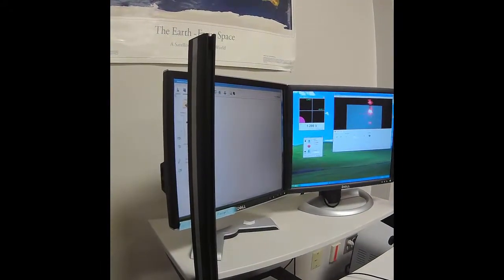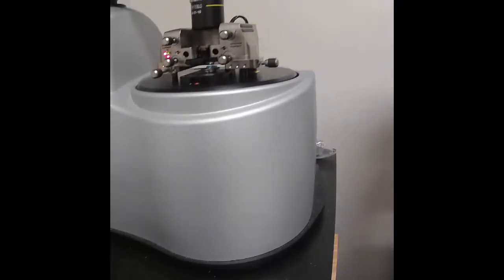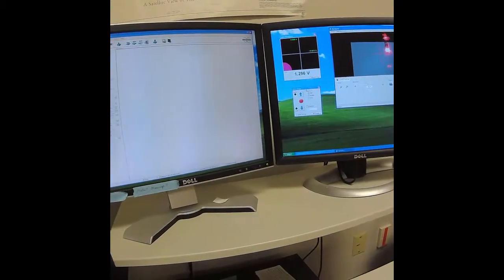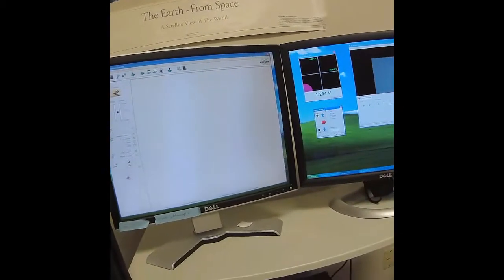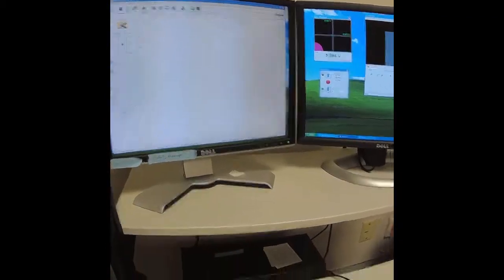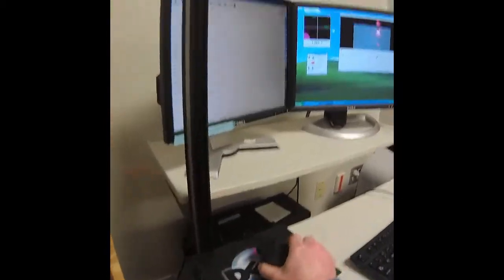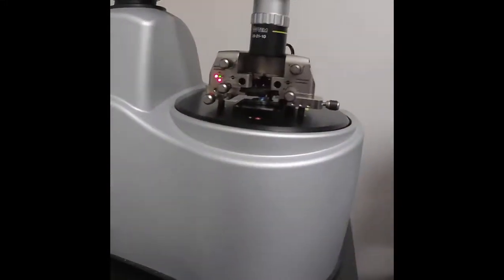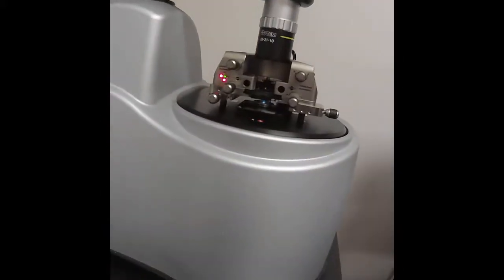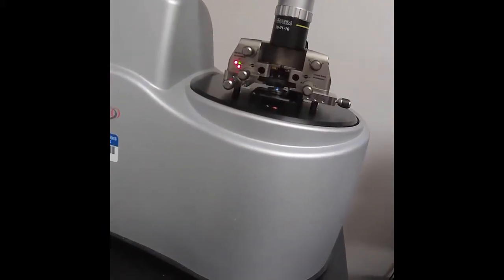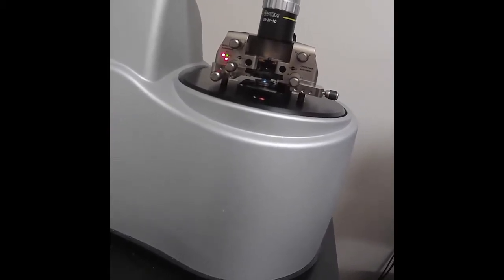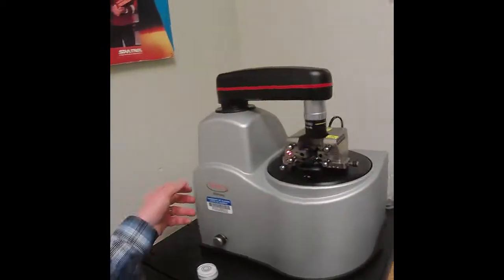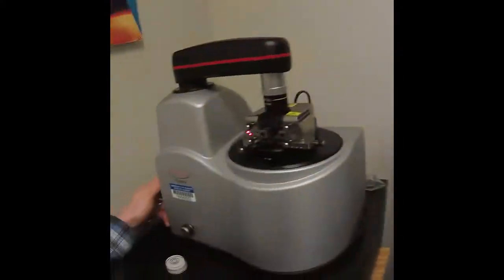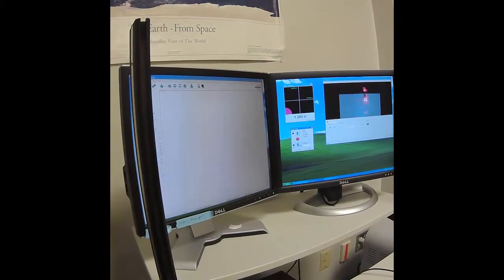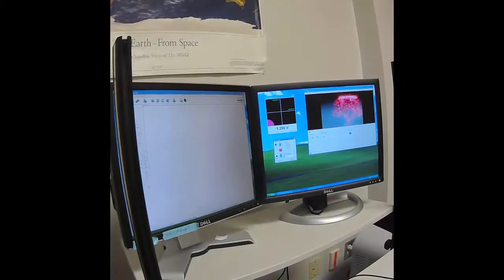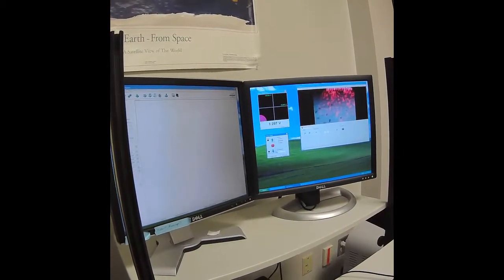Now, is the probe anywhere near the sample surface that we want to scan? We can motor down. Click this button here to get to the motor control. We can motor down the scanner head so that it gets closer to the sample surface. And I do that clockwise. You can see it's moving closer. And we don't want to get too close yet, because we don't want to accidentally crash into the sample surface. So let's look at what the sample surface looks like. Okay, so that's our sample surface.